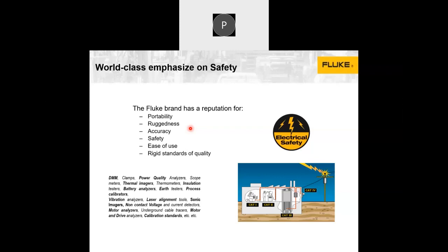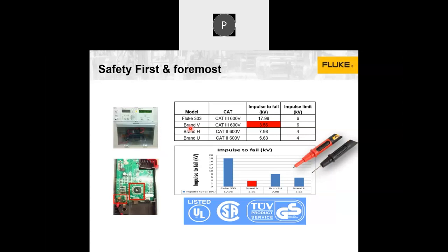And then we comply with all the rigid standards required for that product or application. When I say safety standards, you can see our cheapest clamp meter, which is actually designed for category 3 and 600 volt, we could test it up to 17 or 18 kV. It's supposed to withstand only 6 kV, and we did that test and realized we could go up to that level. We have also conducted a similar study for our own understanding, and we realized that there are brands which actually fail much before the designed levels.